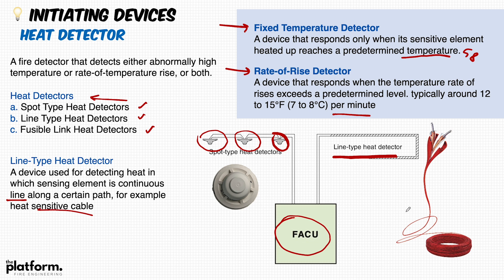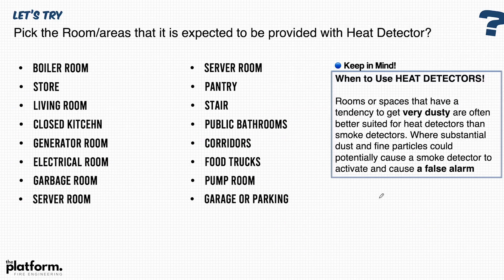The heat detector is one of the initiating devices used in spaces that are likely to become very dusty or where normal smoke could cause a false alarm. When deciding whether to use a smoke detector or a heat detector, the standard procedure is to provide a smoke detector unless there is a chance of dust or smoke being generated in the room that could cause a false alarm — in that case we use a heat detector.